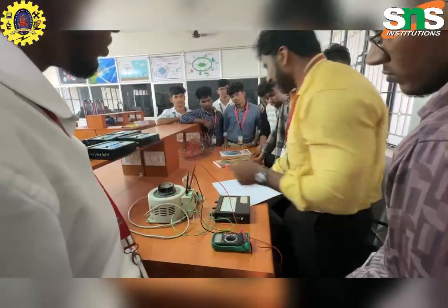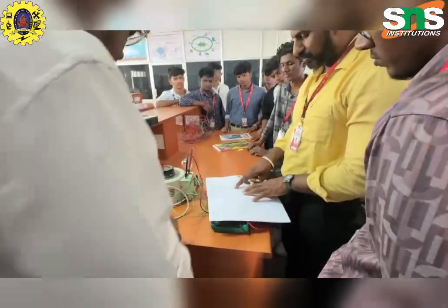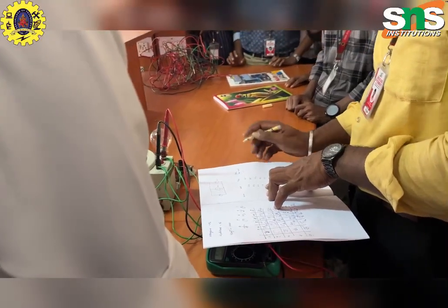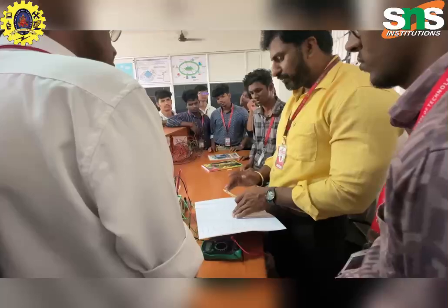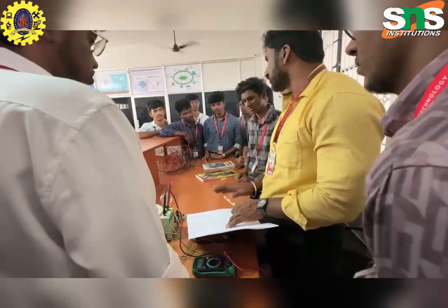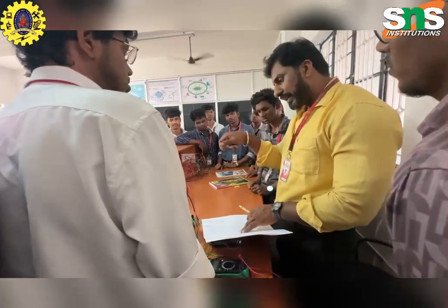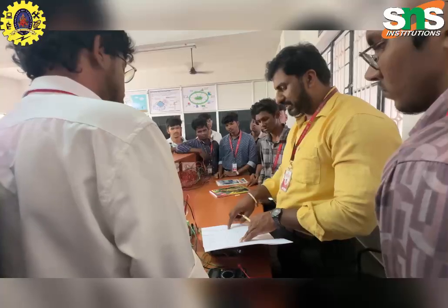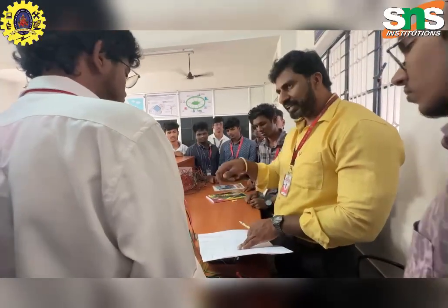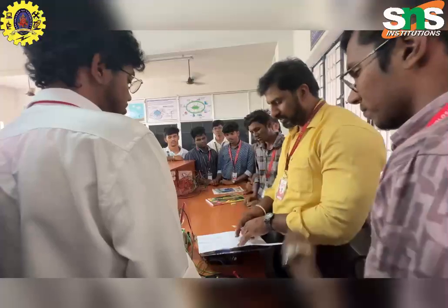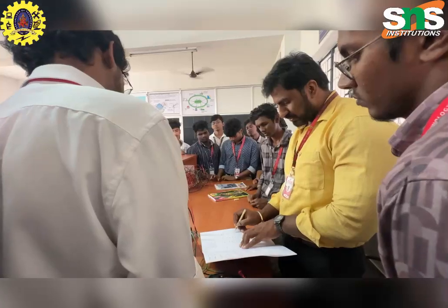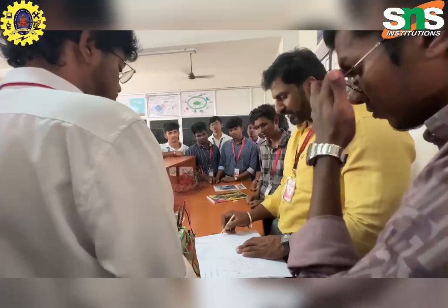Next we are going to calculate the error. The standard value is 62, and the test meter is showing 65. So what is the error? 65 minus 62, that is positive 3. Positive 3 means the meter is leading the reading. The actual value is 62, but the test meter shows plus 3. So we need a negative calibration. Positive error means we need a negative calibration, and negative error means we need a positive calibration. Then 85 and 83 is plus 2, again plus 2, then plus 4, plus 5, and then plus 2. So these will be the errors.